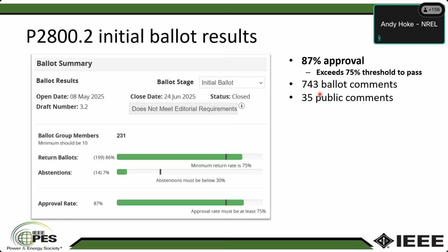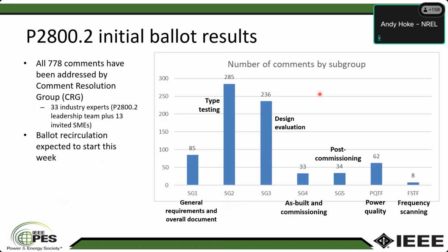So that's sort of the next step, is finishing up this ballot. It'll probably take a couple more rounds just because of the way that the IEEE Standards Association procedures work. If you look at those 700 and something comments and divide them up by topic, you'll see a whole lot of them are on the type testing piece, which is again this testing of a single inverter or turbine or power plant controller to make sure that its performance matches its model. There's also, to some degree, some checking of its performance capabilities in that type testing, but the primary purpose is to make sure that the model matches it.